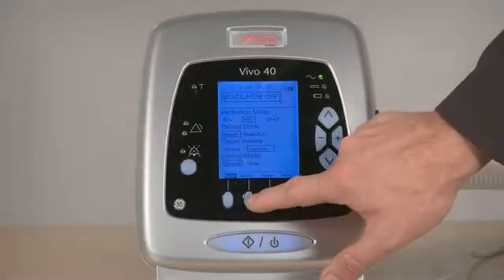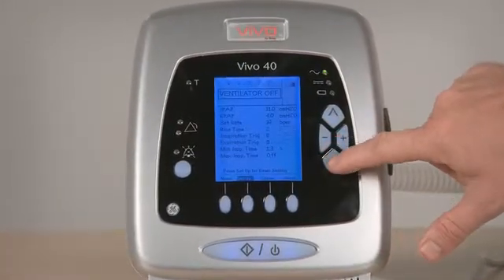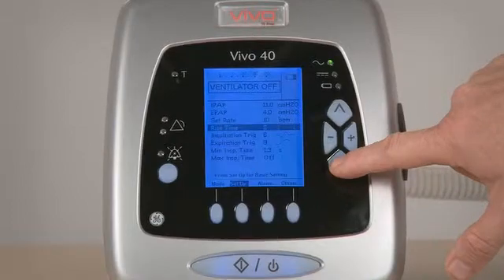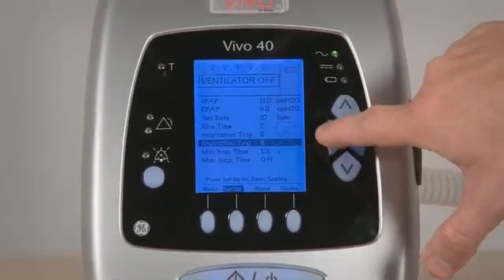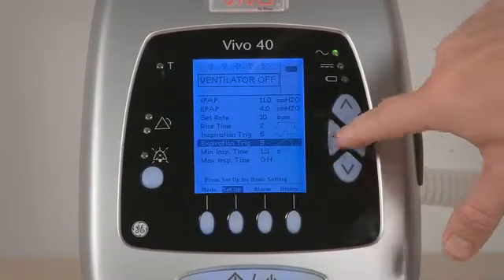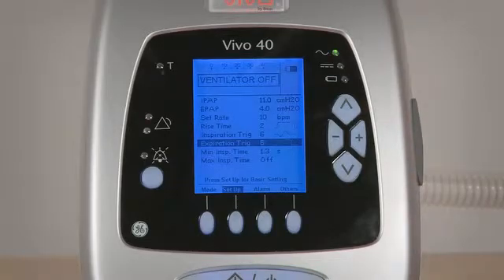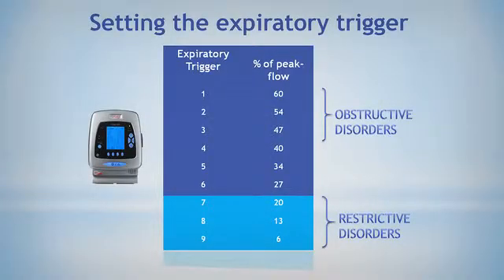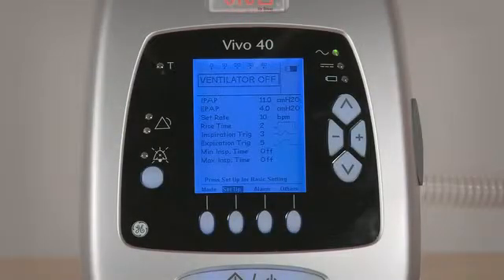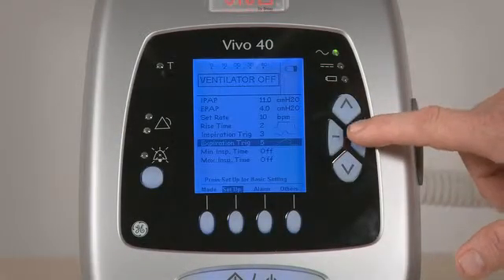In some ventilators, like the Vivo40, the clinician has the option of modifying this value, changing the percentage of peak flow at which the ventilator cycles to expiration. For example, in patients with restrictive disorders like idiopathic kyphoscoliosis, the cycling criterion is usually set at lower values of peak flow to avoid premature termination of breaths.